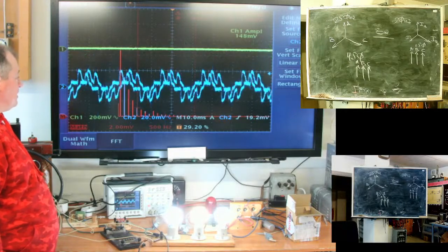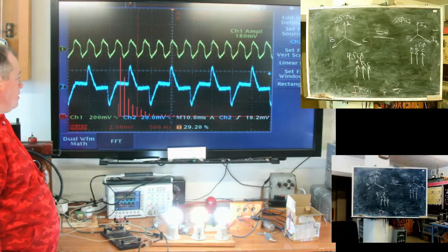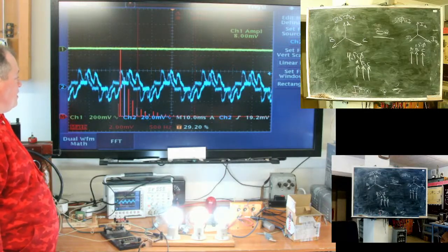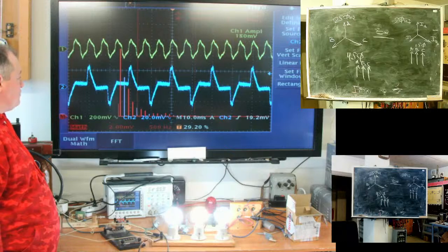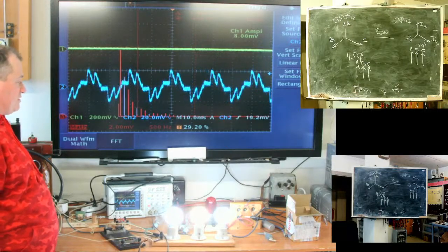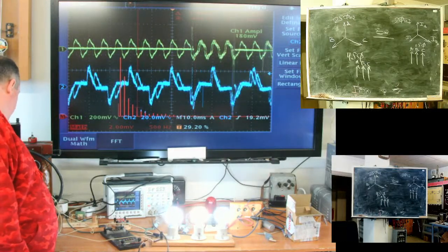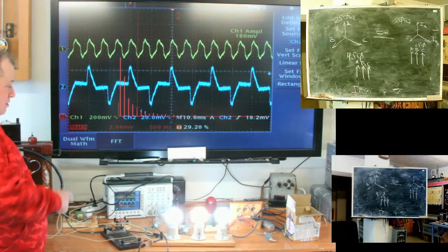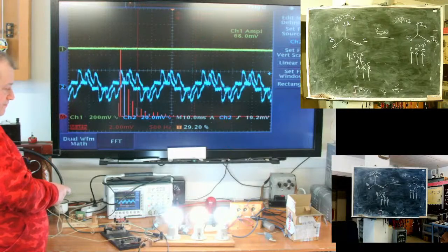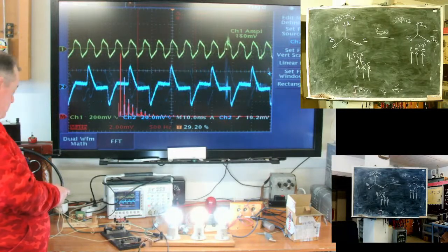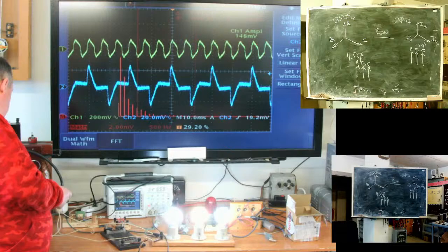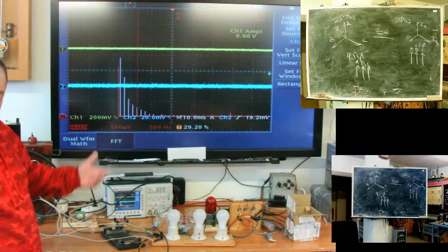See, the third harmonic disappears. And I see an increase in the phase harmonic and in the fifth. With ground wire, without ground wire. And voltage increases. You see? Increase in voltage can cause damage to your client's appliance. Okay, let's go forward.